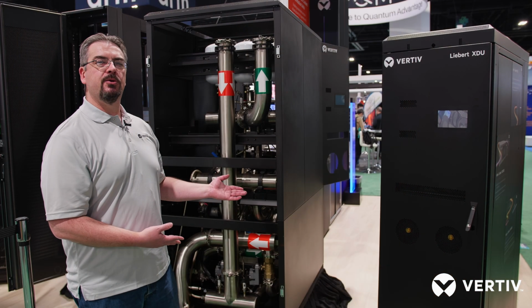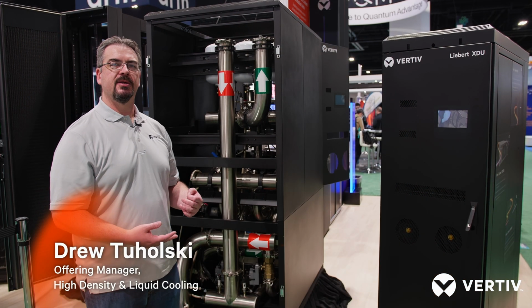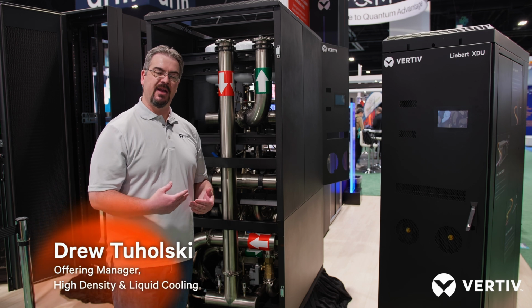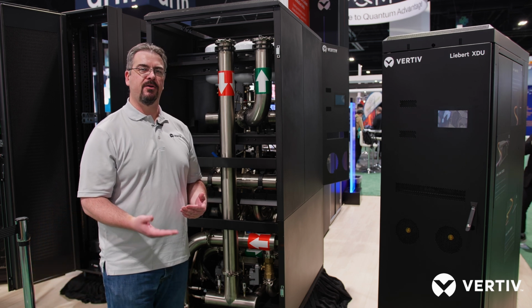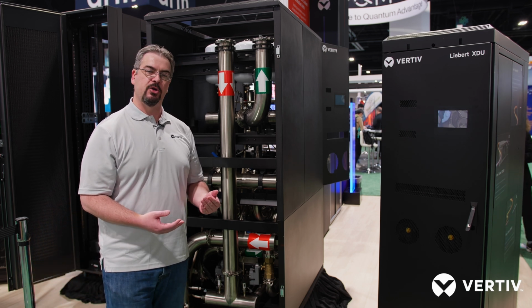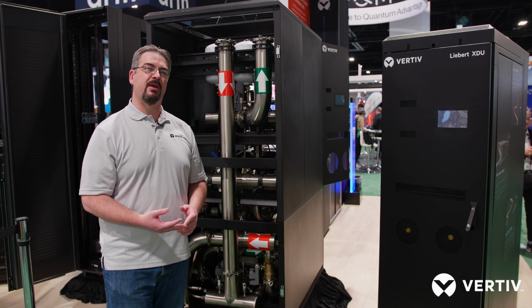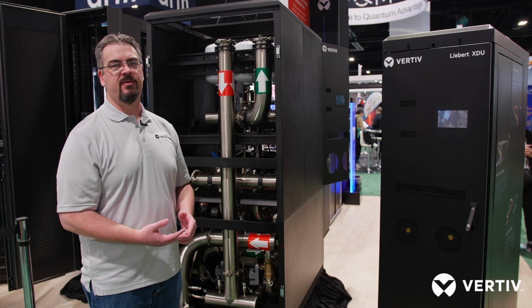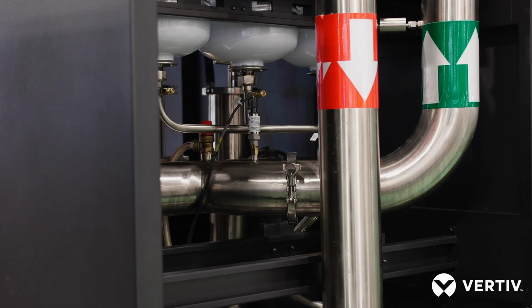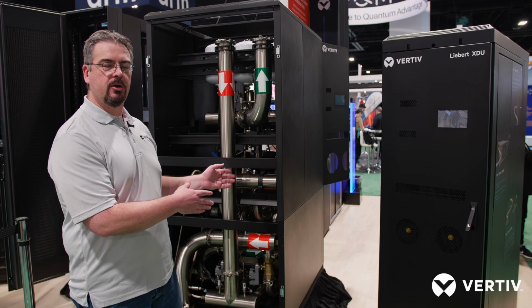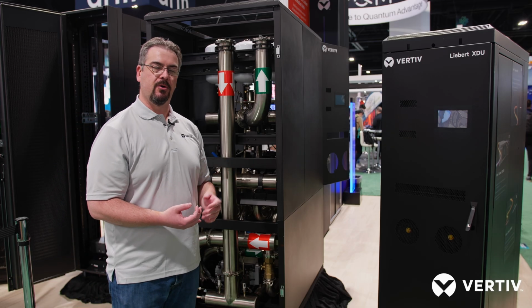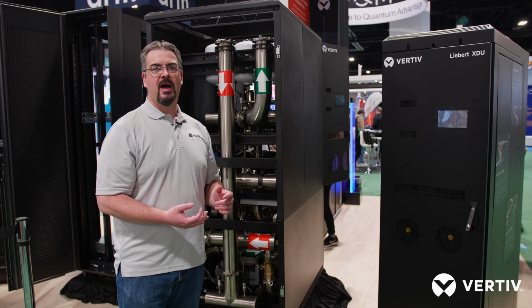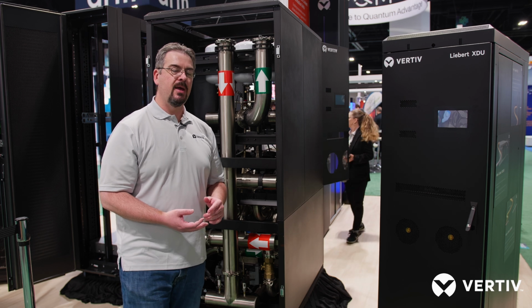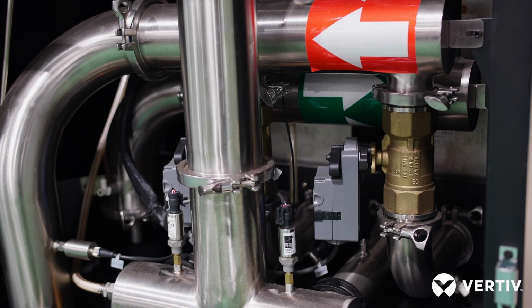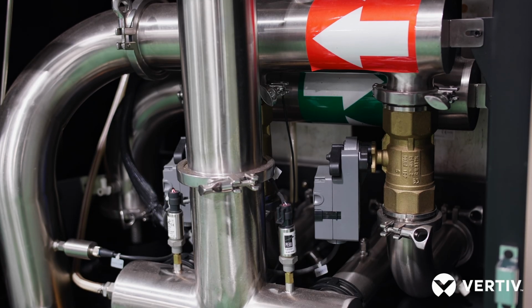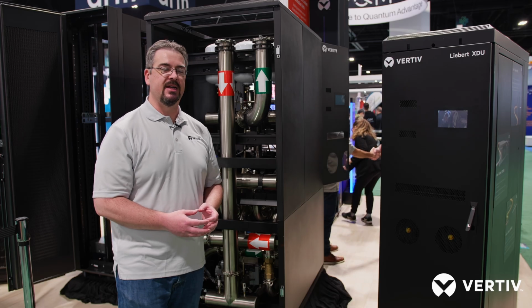The reason CDUs are being installed in data centers is that the liquid cooling we're providing to the rack cannot be supplied directly from the chiller itself. The chiller water might be too cold, it might not be clean enough, it might not be the right type of fluid. So by positioning a CDU between the chiller and the rack, it allows us to control the temperature of the fluid going to the rack, how much flow rate, how much pressure, and especially make sure that we have absolutely clean fluid going to the racks themselves and we don't have any debris contamination.